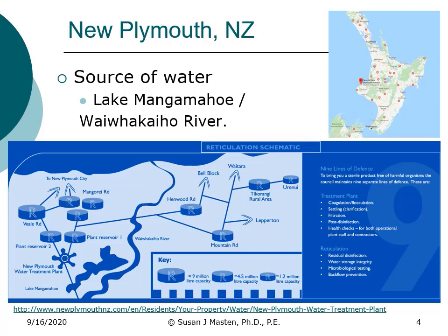It also goes through filtration by screening initially, and then they add powdered activated carbon for taste and odor control. And then they do a pH adjustment with either lime or carbon dioxide. And that then moves into a rapid mix system, followed by coagulation, flocculation, and then further treatment.